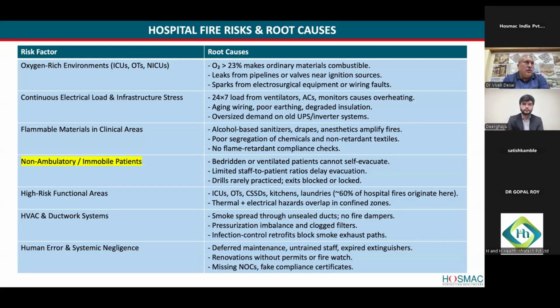One should go for a good quality material when we are seeking, not to look at cost cutting, especially in areas where you have intensive care and critical care. Continuous electrical load and infrastructure stress, and that is what actually is the 85%, 90% cause. So 24/7 load, because we are a building which operates 365 days, 24 hours throughout. So there is an air conditioning system which keeps working, there are ventilators in ICUs, monitors, which all cause overheating, and the aging wiring, poor earthing, degraded insulation, oversized demand on old UPS inverter systems. So these are the kind of things which are there.